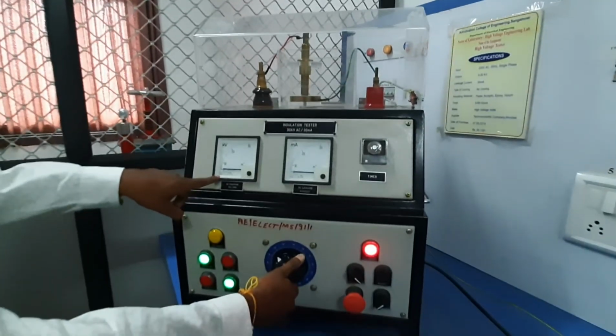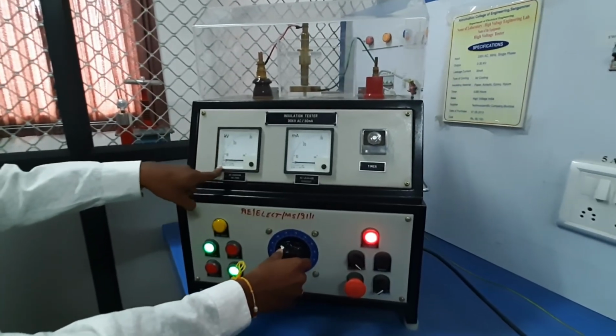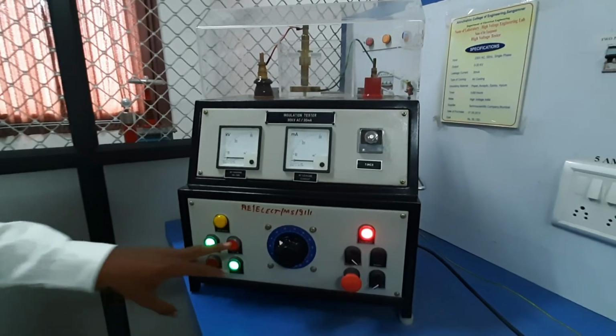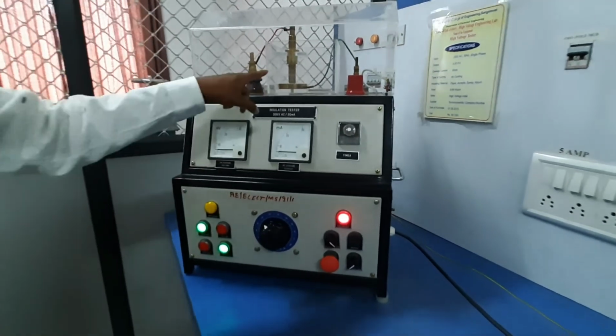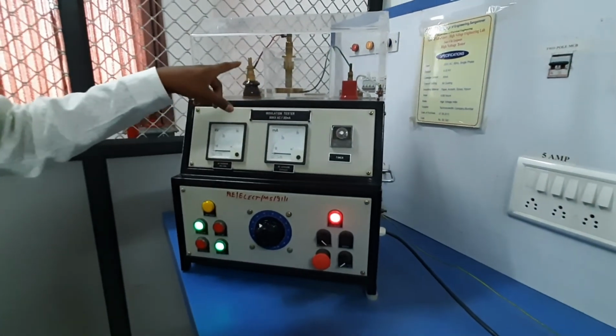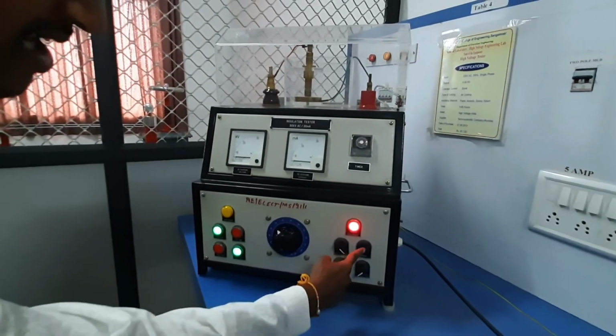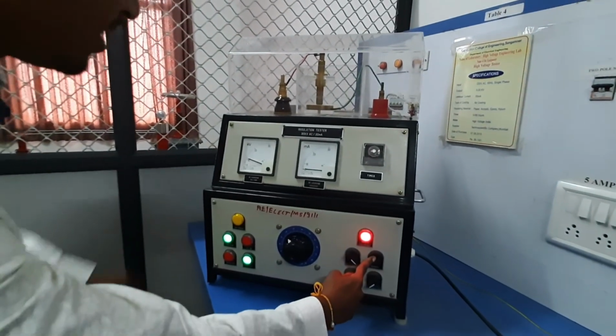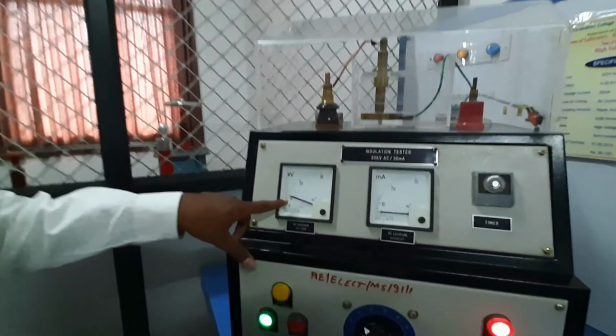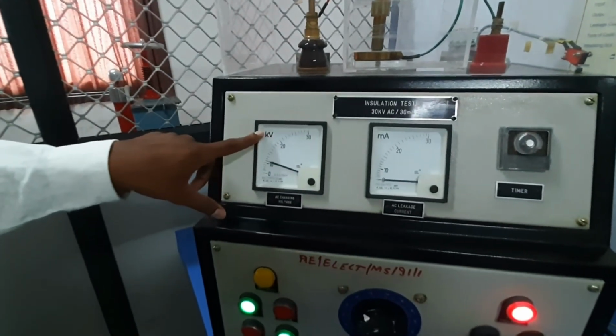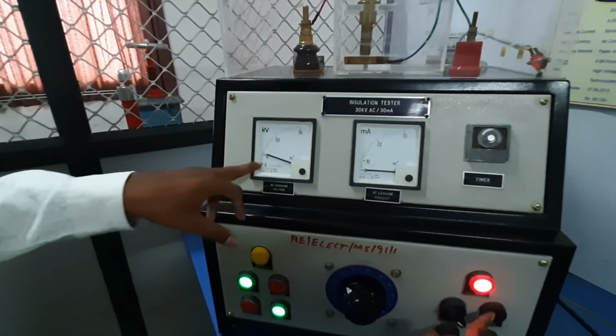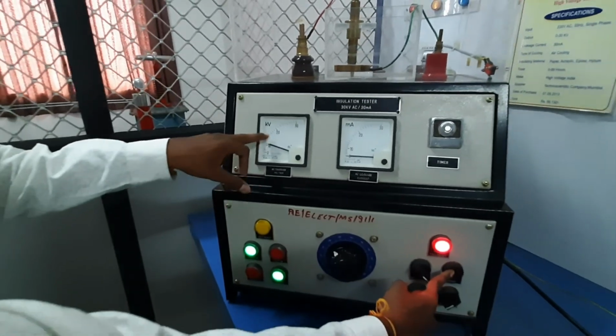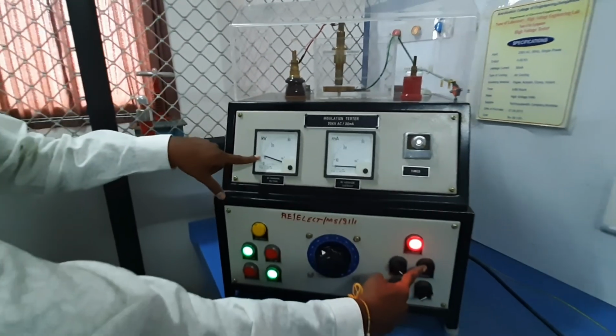Here breakdown occurs in this material. To check the breakdown for this paper insulating material, we press the memory button, and it shows a reading of 11 kV. This shows that breakdown occurred at 11 kV.